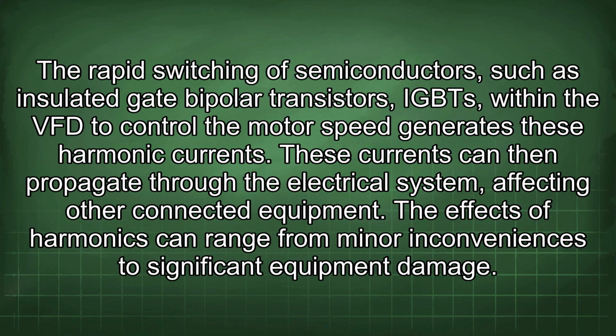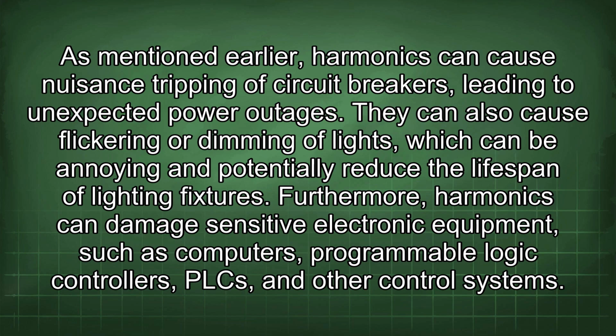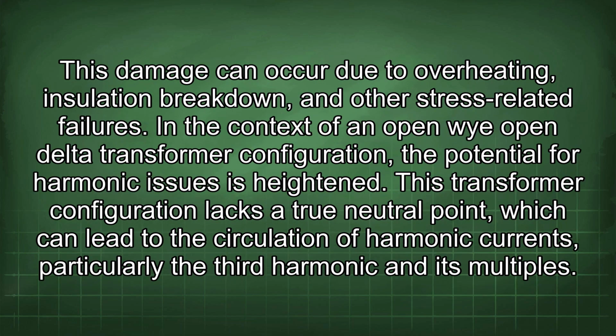The rapid switching of semiconductors, such as insulated gate bipolar transistors (IGBTs), within the VFD to control the motor speed generates these harmonic currents. These currents can then propagate through the electrical system, affecting other connected equipment. The effects of harmonics can range from minor inconveniences to significant equipment damage. As mentioned earlier, harmonics can cause nuisance tripping of circuit breakers, leading to unexpected power outages. They can also cause flickering or dimming of lights, which can be annoying and potentially reduce the lifespan of lighting fixtures. Furthermore, harmonics can damage sensitive electronic equipment, such as computers, programmable logic controllers (PLCs), and other control systems. This damage can occur due to overheating, insulation breakdown, and other stress-related failures.